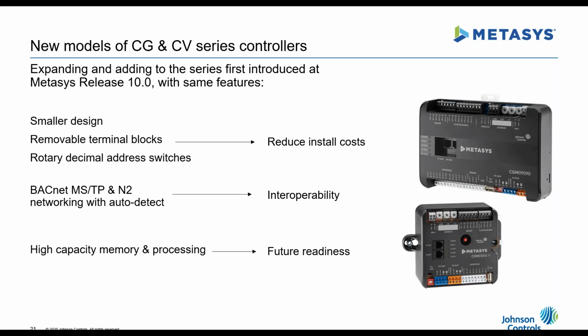These models feature removable screw terminals for all field wiring connections that allow for convenient, quick, and easy installation and servicing. They also feature rotary dial switches for device addressing, making it easier to set and read addresses without needing to manually convert from binary to decimal as you do with dip switches on the existing FEC family of controllers. All these features make it more efficient for technicians to work on them and can lead to a reduction in installation and service costs.